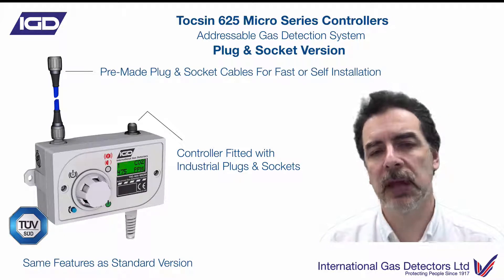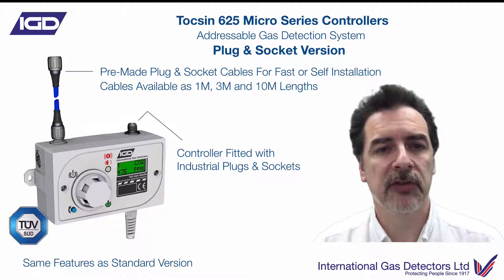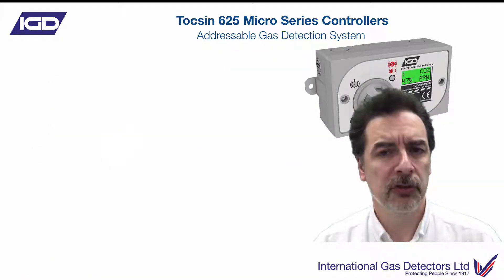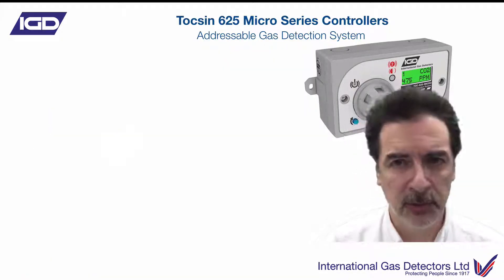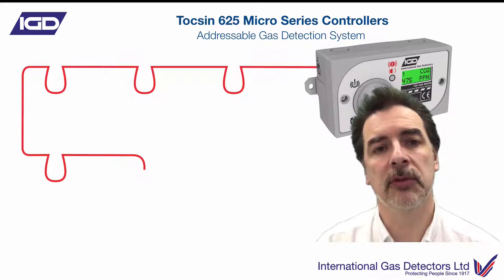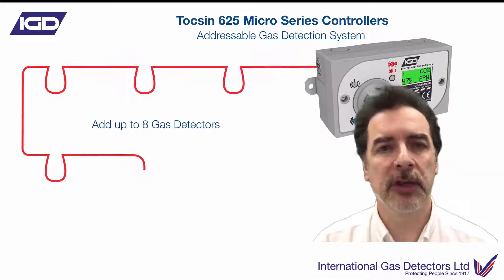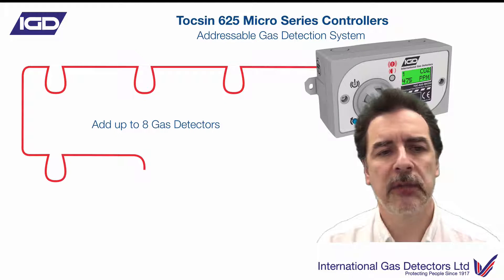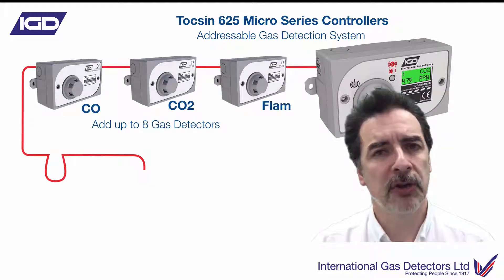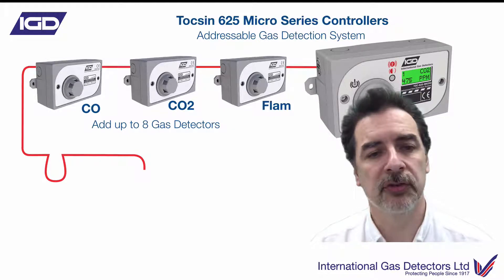The cables we supply are pre-made. They come in one meter, three meter and ten meter lengths, and you can plug those together to make up longer lengths if required. When installing, you put your controller on the wall, install either your pre-made cables or conduit runs to the detectors. Up to eight detectors on this system and they can be any variety — here we've got CO, CO2 and FLAM, but any from the Tocsin 625 range can be installed in any combination.